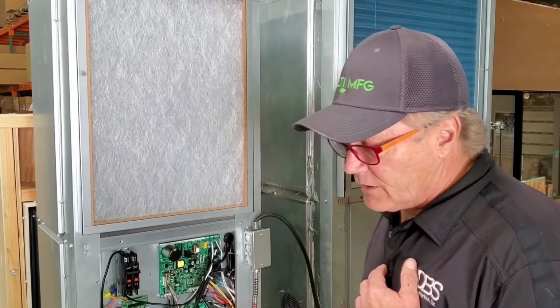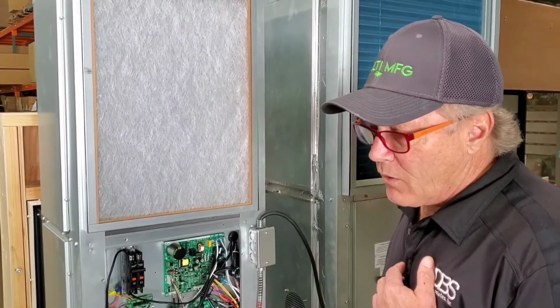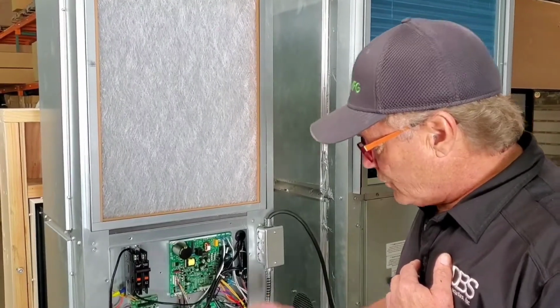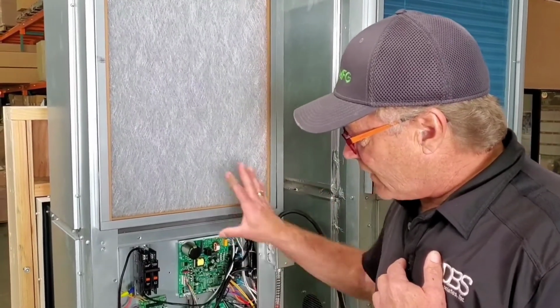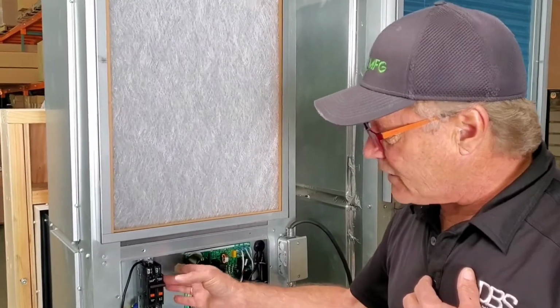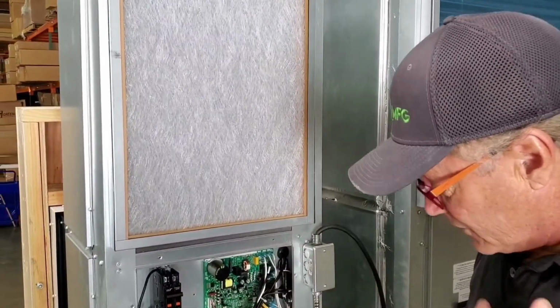This unit is designed to run at almost a third of the power of your previous equipment. So when you're putting in a unit that says 5 kW, don't expect to be pulling 5 kW except for when it goes into defrost mode.